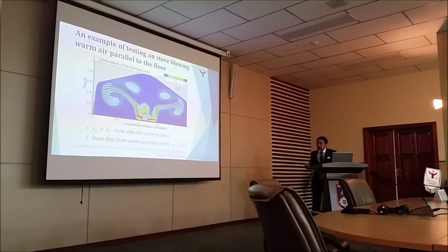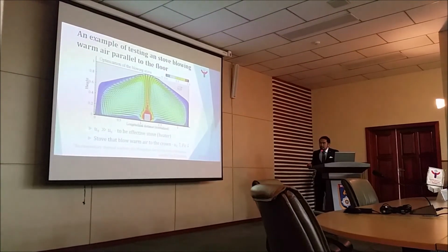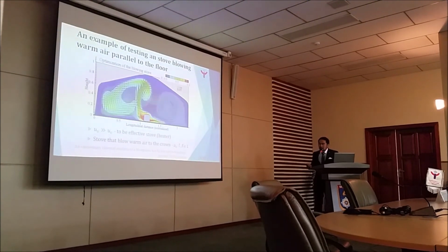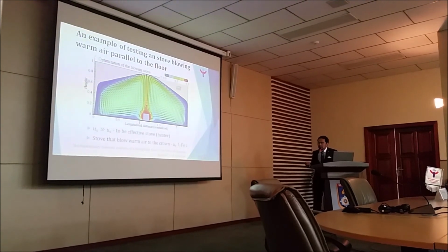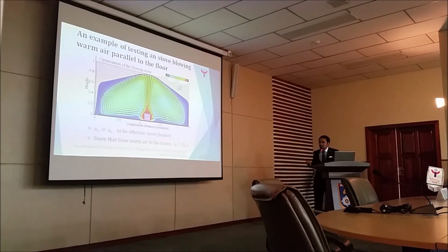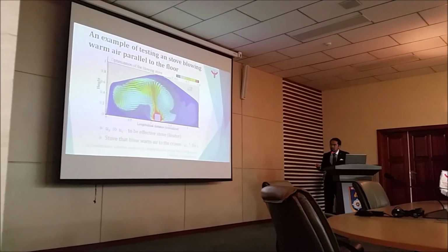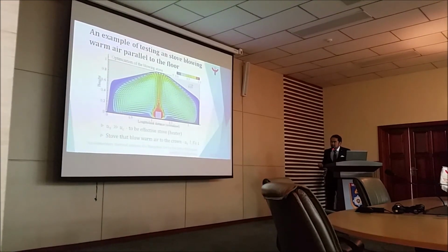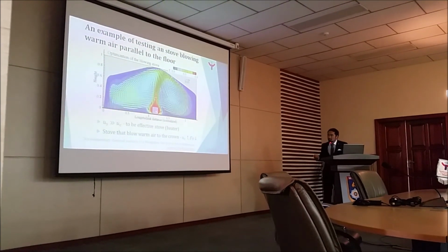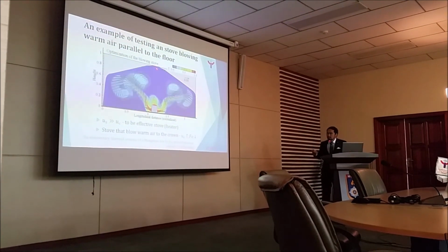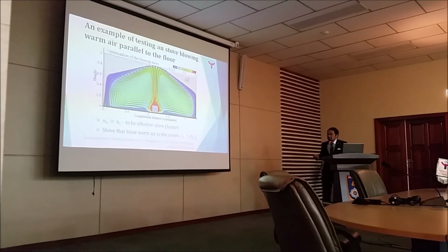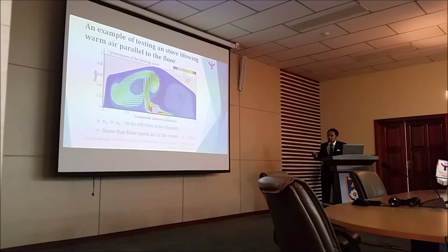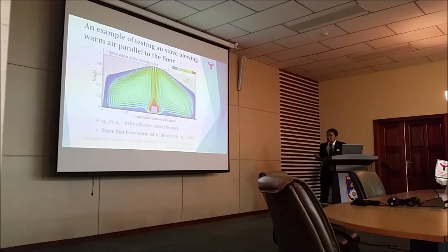And this simple simulation drives two ideas. The first one is that the blowing velocity must be much higher than the convection velocity to be an effective heater, if we design the heater to blow air along the floor. And the second one is a new idea: that we can also blow air to the crown. This will accelerate the velocity of the convection, and then we can reduce the time for the Ger to get warm.